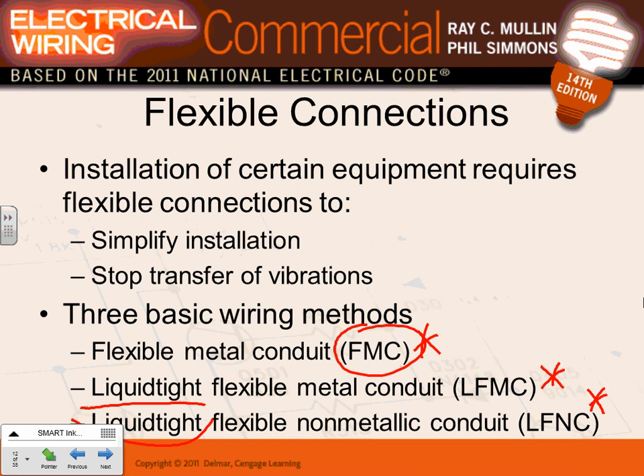If it has liquid-tight, use it in a wet location. If it doesn't have liquid-tight, use it in a dry location. What's the difference between liquid-tight flexible metallic and liquid-tight flexible non-metallic? Anything non-metallic is ideal for a highly corrosive environment. So if you have a machine in a highly corrosive environment and want to tie to it, liquid-tight flexible non-metallic conduit becomes ideal.